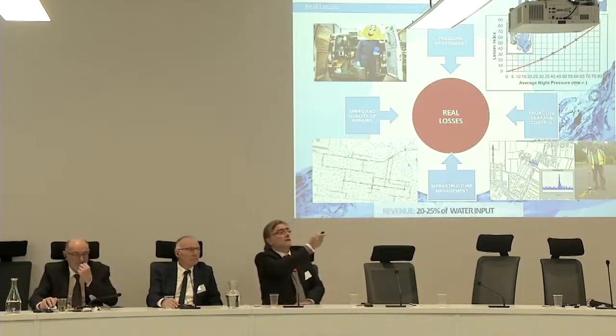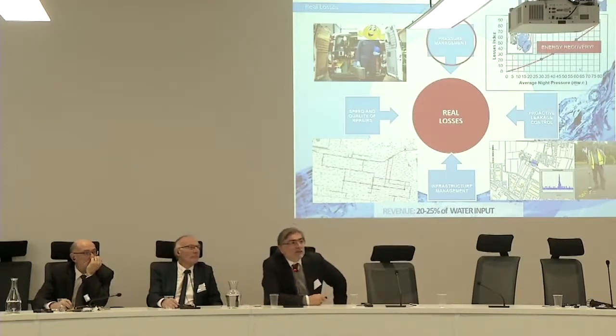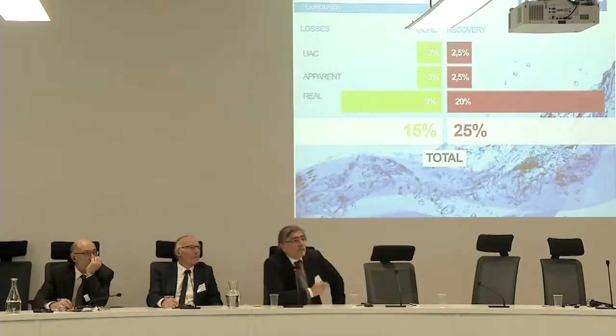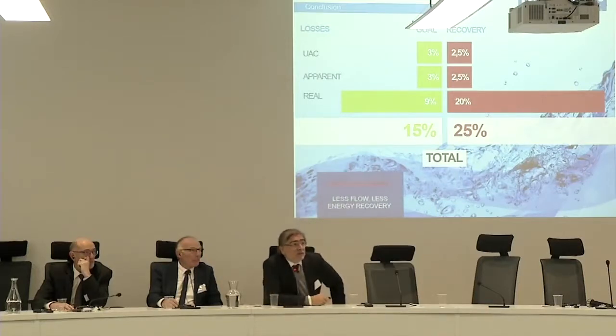Where do I point? Oh, okay. So, in this point, we have the possibility of an energy recovery. But this is the goal of the Portuguese law, 15%. We have 25%. So, as you see, the real losses are the biggest component and the one that, for the purpose of using PATs, is an enemy. So, you have less flow, you'll have less energy recovery.